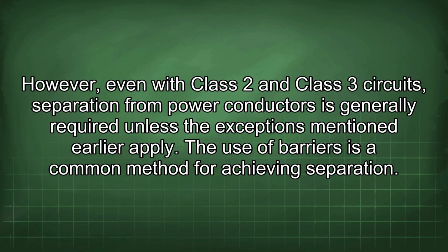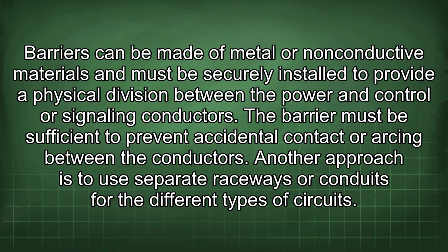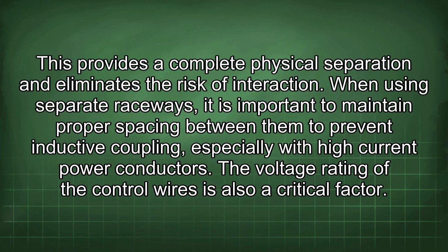The use of barriers is a common method for achieving separation. Barriers can be made of metal or non-conductive materials and must be securely installed to provide a physical division between the power and control or signaling conductors. The barrier must be sufficient to prevent accidental contact or arcing between the conductors. Another approach is to use separate raceways or conduits for the different types of circuits. This provides a complete physical separation and eliminates the risk of interaction. When using separate raceways, it is important to maintain proper spacing between them to prevent inductive coupling, especially with high current power conductors. The voltage rating of the control wires is also a critical factor.